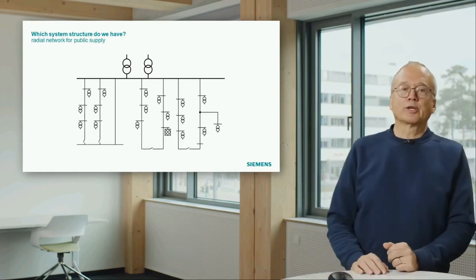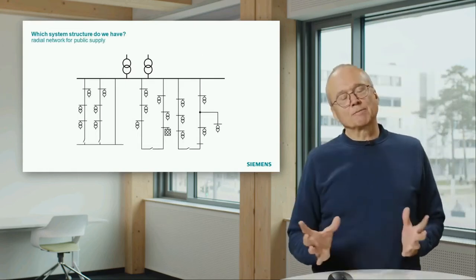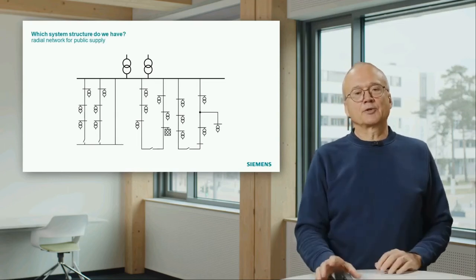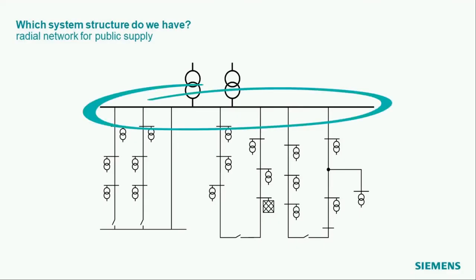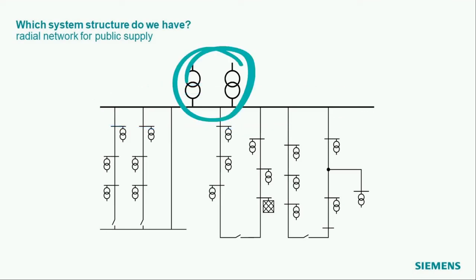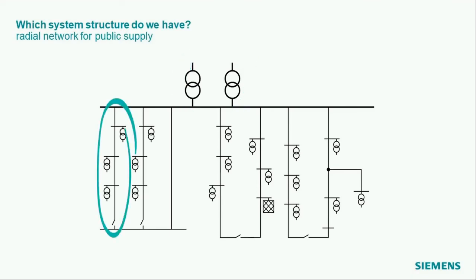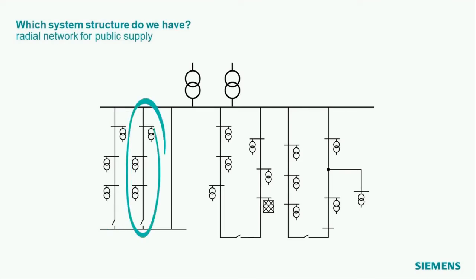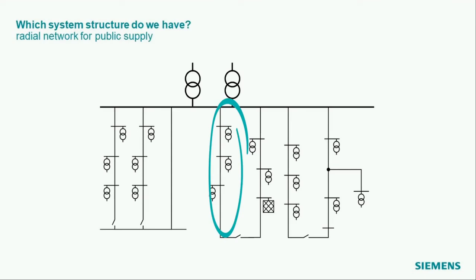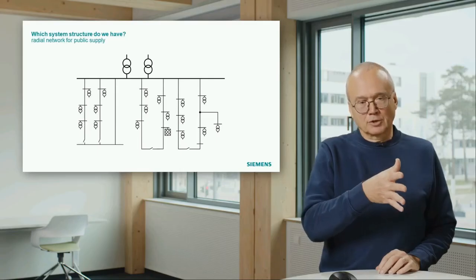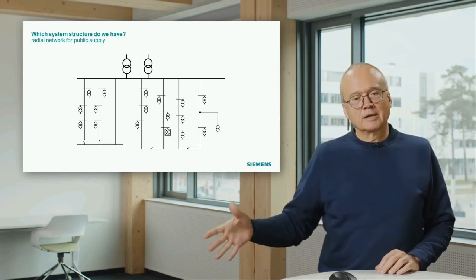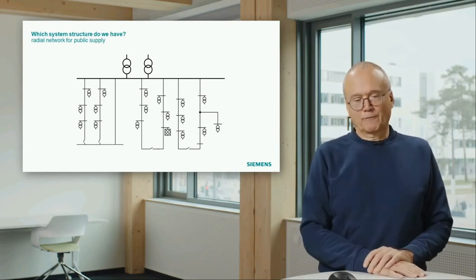Another type of network is shown here. That is a typical network we often find in distribution systems. We have one busbar, which gets its energy from in-feeding transformers. And then from the busbar, we have so-called radial feeders. That means feeders with different substations, transformer stations in between. And these transformers transform down from the distribution level, 20 kV, to the low voltage level, 0.4 kV.